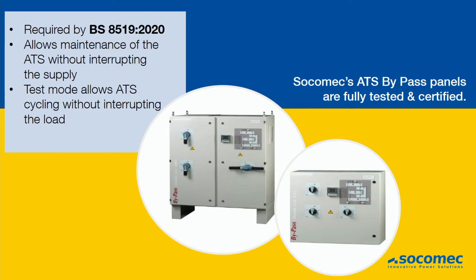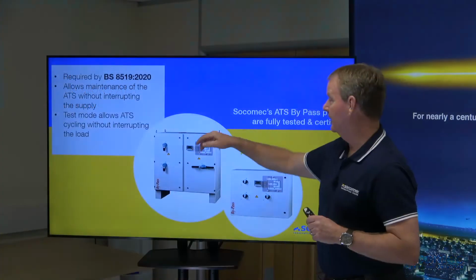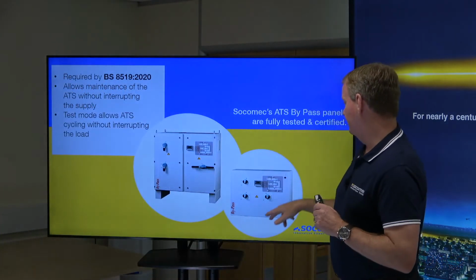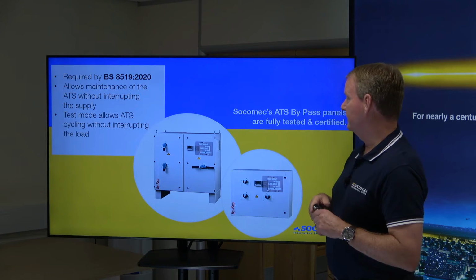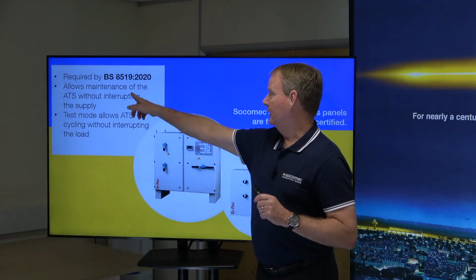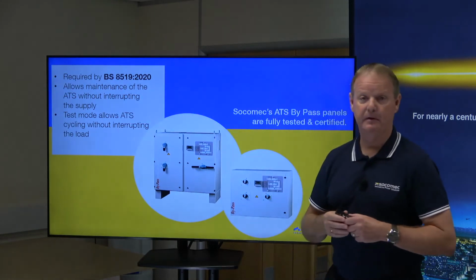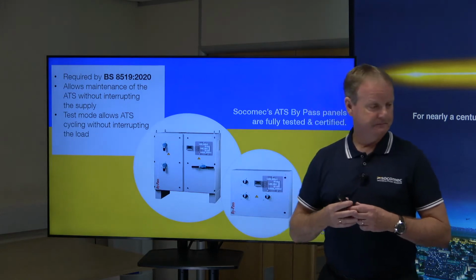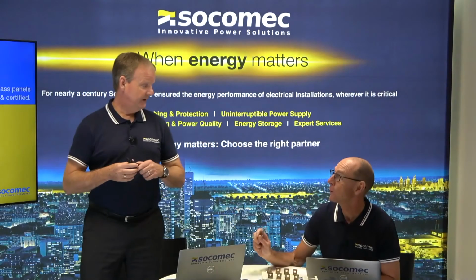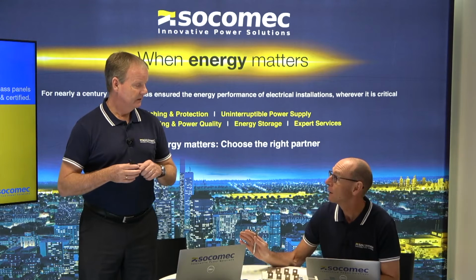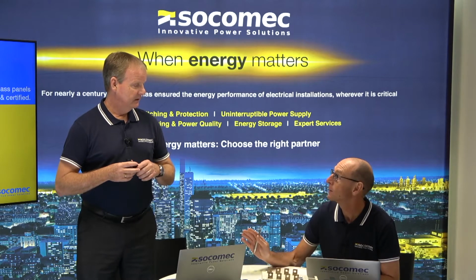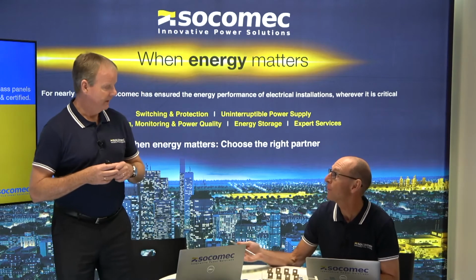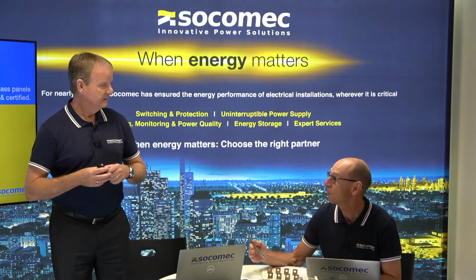So here's an image of some ATS bypasses. As you can see, it's required by BS 8519/2020. Okay, you've got a 2-door system here and a single door system here. And this, as I said before, allows for maintenance of the ATS without interrupting the supply. So just to reiterate again, to be compliant with 8519, you have to provide a bypass, to be able to carry out maintenance, yes, but still have the supply available for the critical equipment.